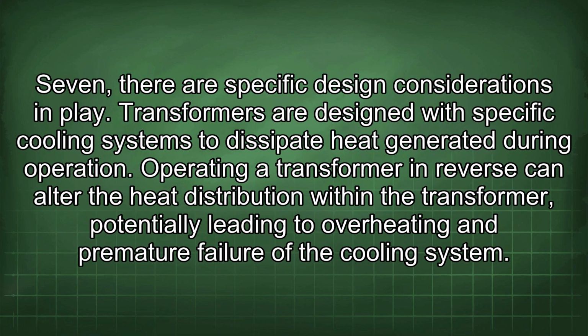7. There are specific design considerations in play. Transformers are designed with specific cooling systems to dissipate heat generated during operation. Operating a transformer in reverse can alter the heat distribution within the transformer, potentially leading to overheating and premature failure of the cooling system.